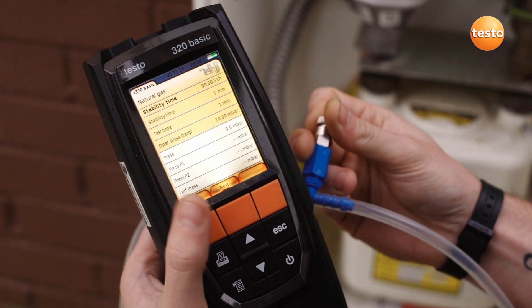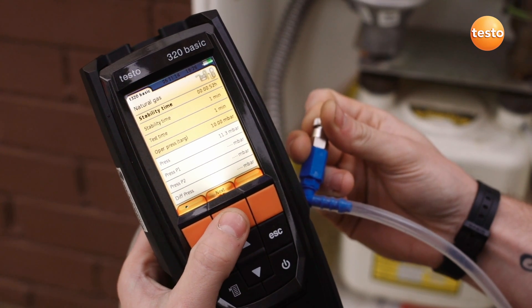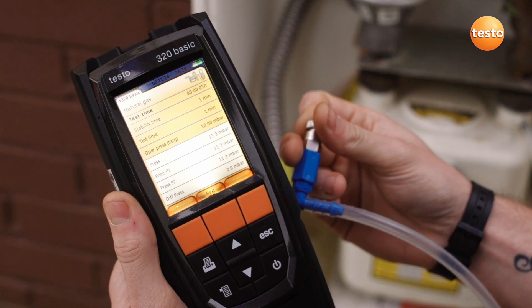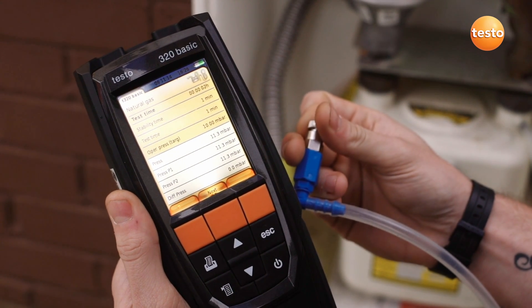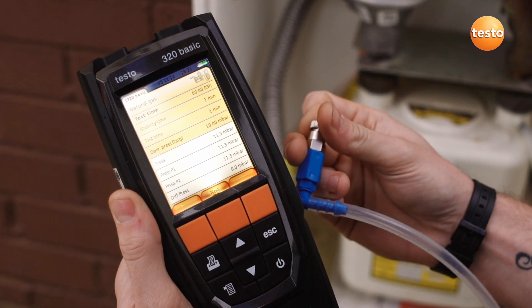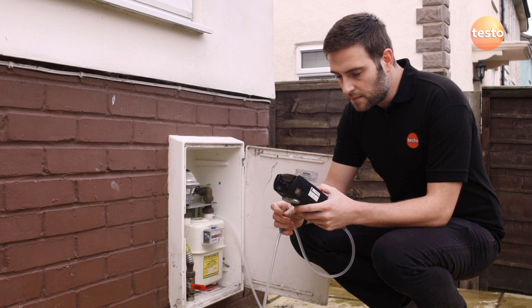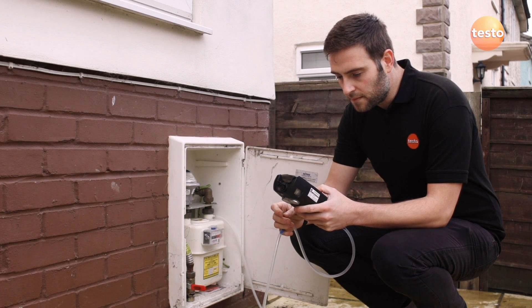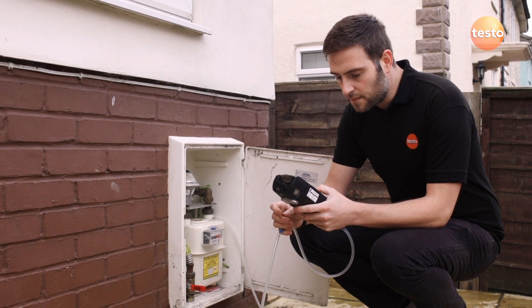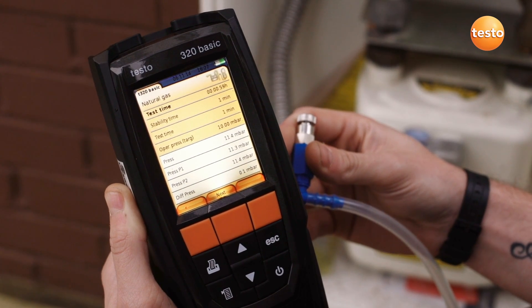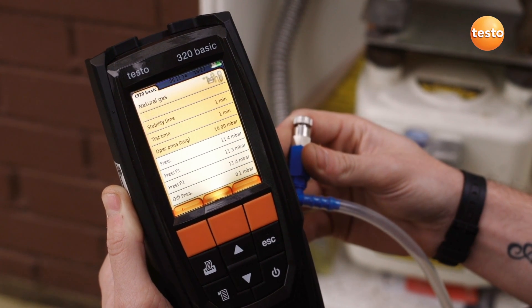At the end of the stability test, the analyzer immediately goes into the timed let-by test where it measures and logs pressure for the preset test time. During the test, it displays the pressure at the beginning, the current measured value, and the difference.